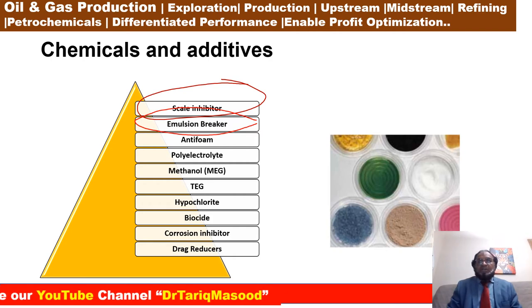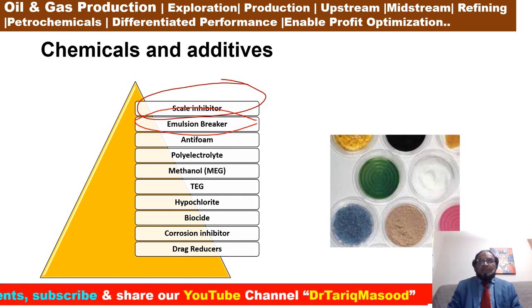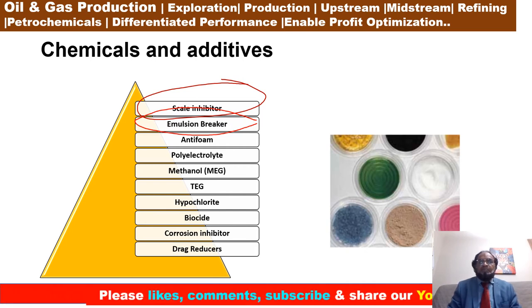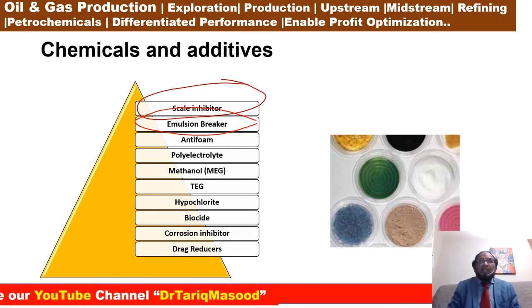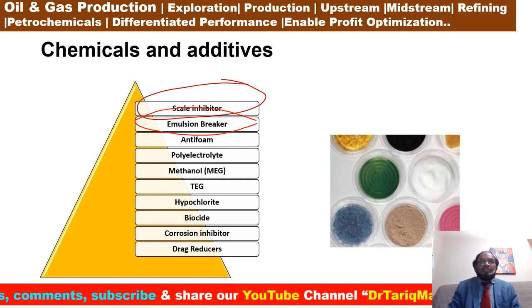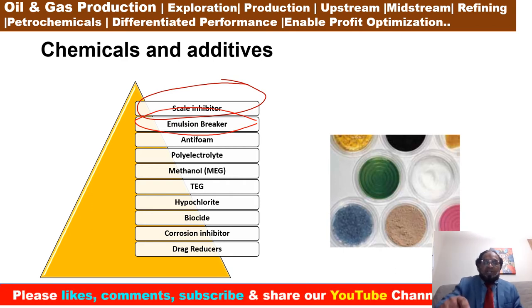Sand and particles are normally carried out by the water extractor in the water treatment. However, the emulsions can trap these particles, which sink to the bottom as a sticky sludge that is difficult to remove during operation. Although the emulsion layers will eventually break down naturally, it takes too much time. An emulsion breaker is added to prevent formation and promote a breakdown of the emulsion layers by causing the droplets to merge and grow. Okay, second is the antifoam.